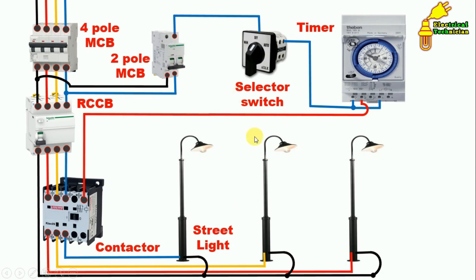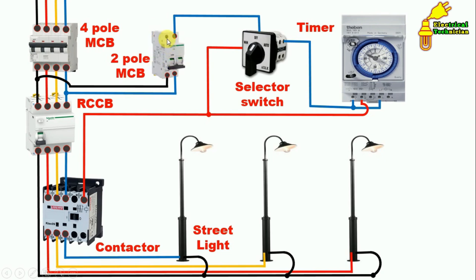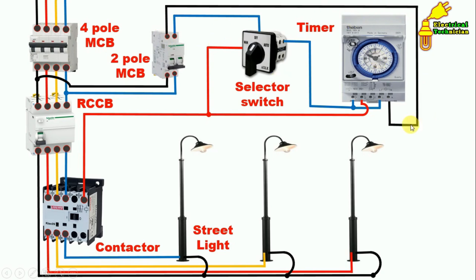For manual mode, change the selector switch to manual position. From the wire connected here, get continuity to the manual terminals and connect a wire with the A1 terminal of the contactor. When the selector switch is in manual position, power supply goes directly to the contactor; in auto position, power supply goes through the timer. For neutral supply, from the outgoing terminal of the MCB connect a wire to the neutral terminal of the timer, then loop a wire from there to provide neutral supply to the contactor.